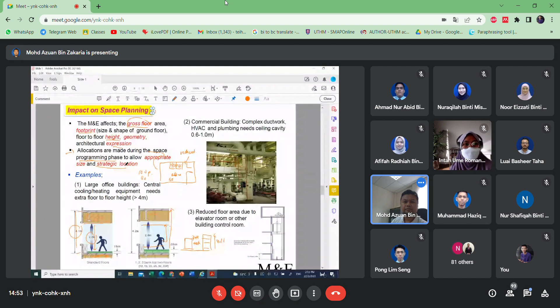Okay, how many percent? For example, computer center, the range is from 10% to 30%, depending on the type of occupancy. Type of occupancy means the size of building. If it is a small computer center, maybe 10% of the area is for M&E system. But for a big or large computer center, it needs a larger percentage of gross floor area for the M&E system.